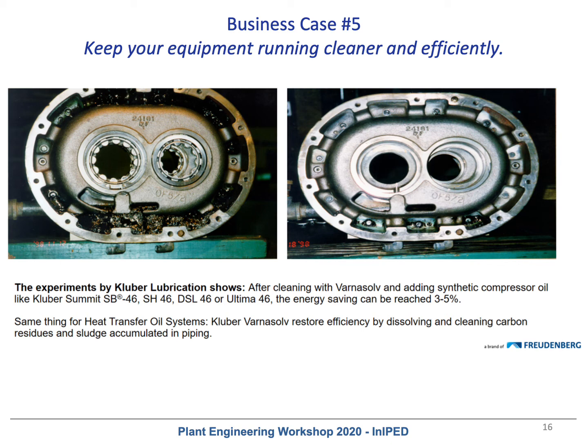Most of the time, chemical companies and also pulp and paper companies use really large heat transfer oil systems. They could be for heat exchangers, for boilers, and also to heat trace the piping inside a chemical or petrochemical plant complex. So Kluber Varnasolv will most of the time be really beneficial for the system, as the oil will break down thermally in the system, and the system could contain over 300,000 liters of oil, and sometimes it's exposed to over 250 degrees Celsius. And with these large systems, these companies don't want to change the oil every year, and most of the time will prolong the service life of the heat transfer oil to over 10 years.